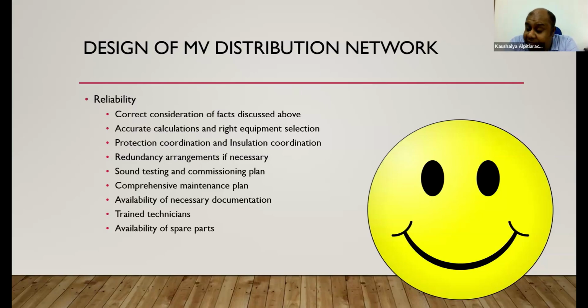Redundancy arrangements, if necessary. Take a hospital or a data center or a critical application, you need redundancy. Maybe you need more than one MV feeder. The designer should decide whether you are going to maintain the redundancy through the medium voltage side or through the low voltage side. Whatever it is, redundancy will be a key factor for a critical installation.